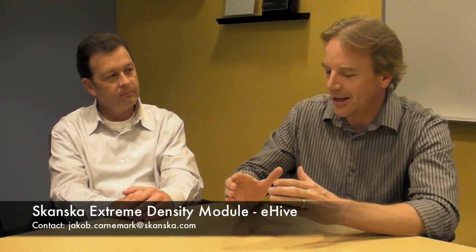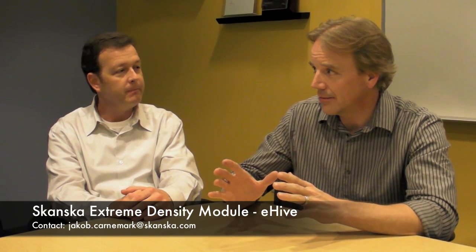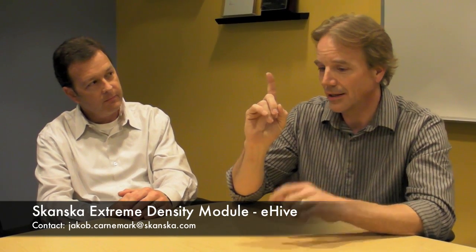Because ultimately, this solution, and we'll talk about it more in a future episode, really does get to extreme density. It really gets to extreme efficiency. And when you've got cabinets going 20, 30, 40 kilowatts, because now we really understand how IT and facilities work together to get that ultimate efficiency, you've got to have solutions that can handle that. And there aren't that many solutions out there that can do that. You can't just open the window and take enough air in to cool a 40 kilowatt cabinet. No, you can't. That's something that takes a lot of research and very precise engineering. You don't fake 40 kilowatts a cabinet. You just don't do it.